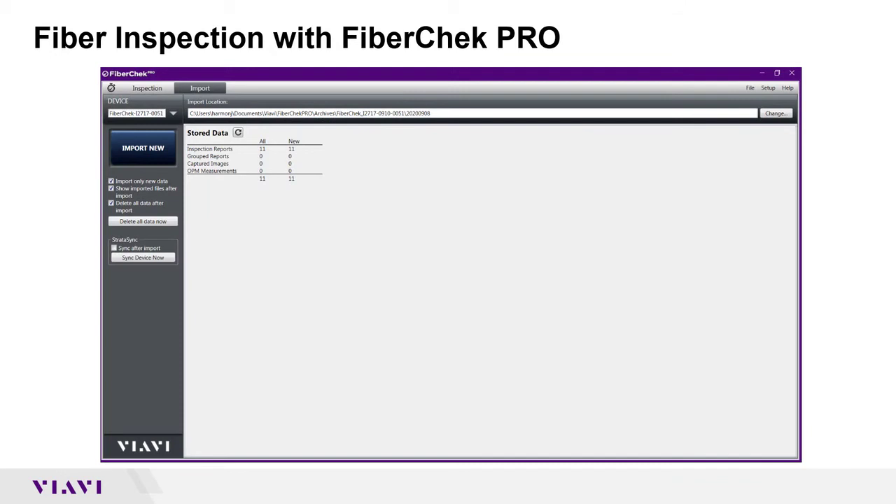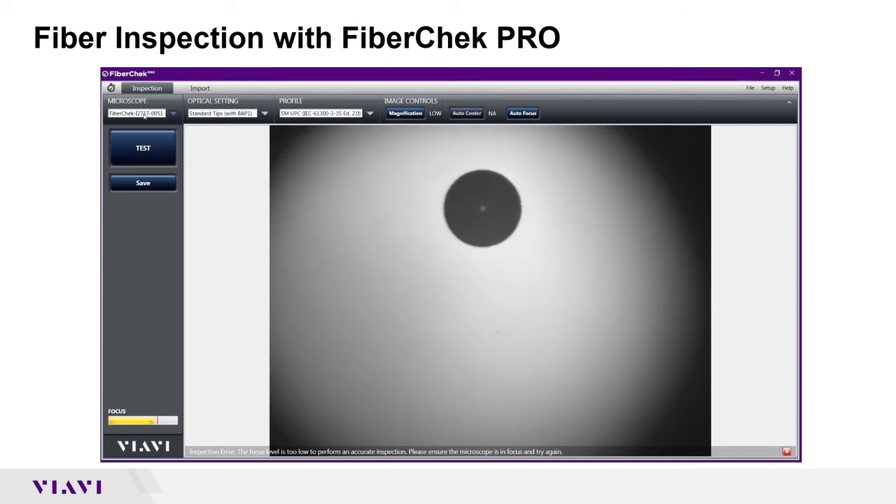You can now plug your fiber in to the FiberChek probe. I've launched the FiberChek Pro software. By default we come into the import screen, and up to the left I'm going to touch on inspection. Below there it has the microscope. In this case I have the FiberChek and there's my serial number. To the right of that I have my tip selections and I can click on that. Right now I have standard tips.